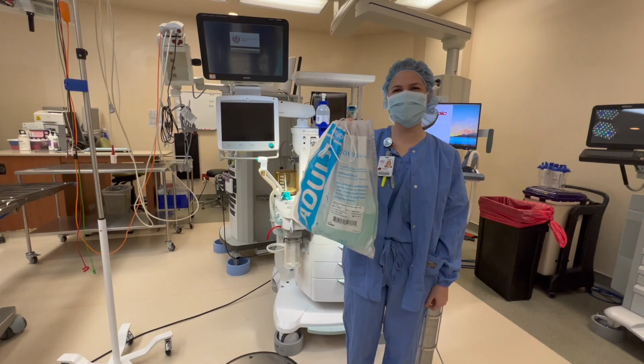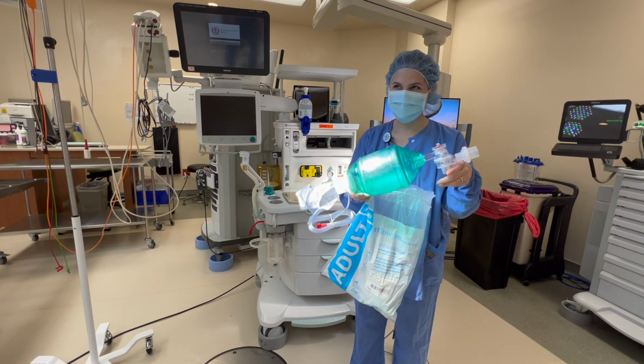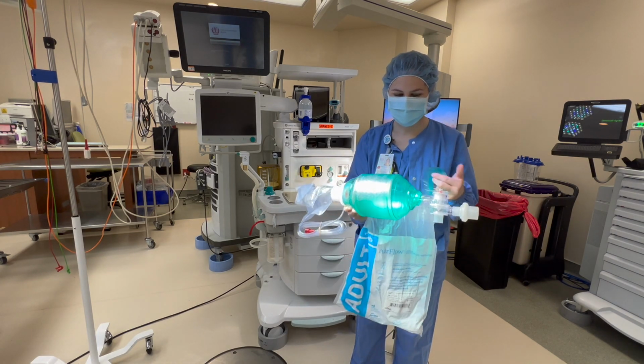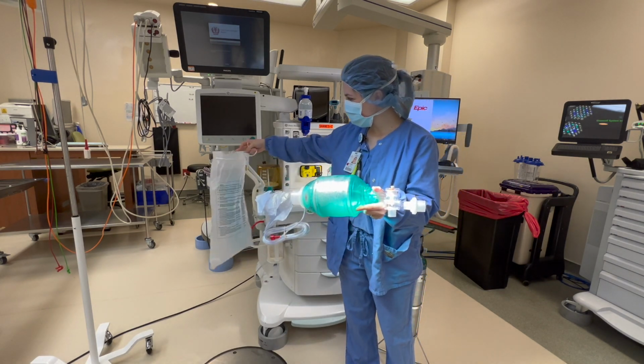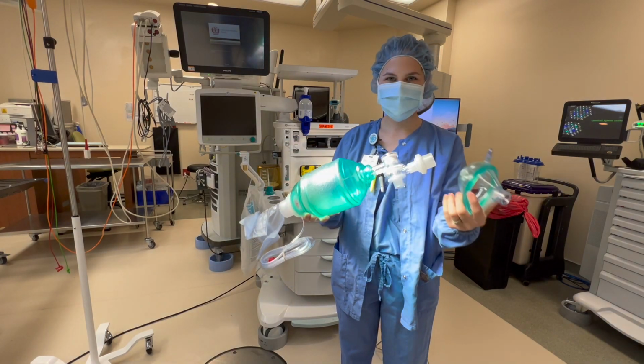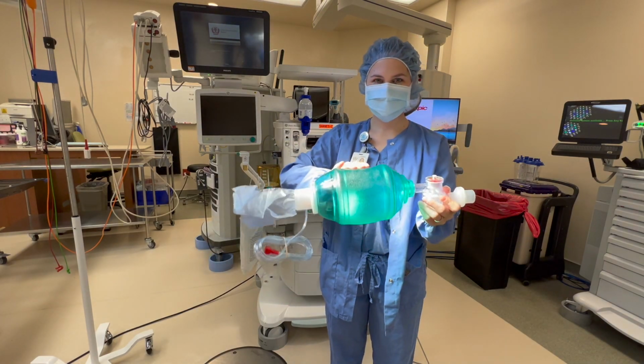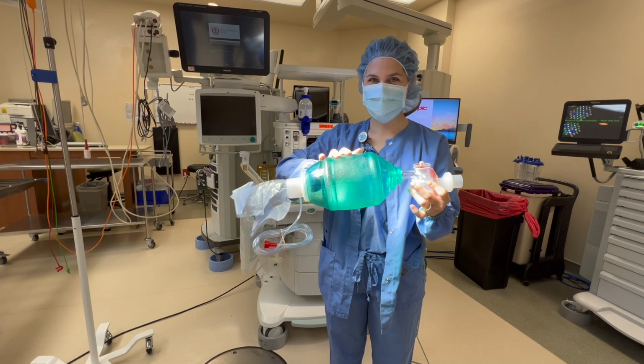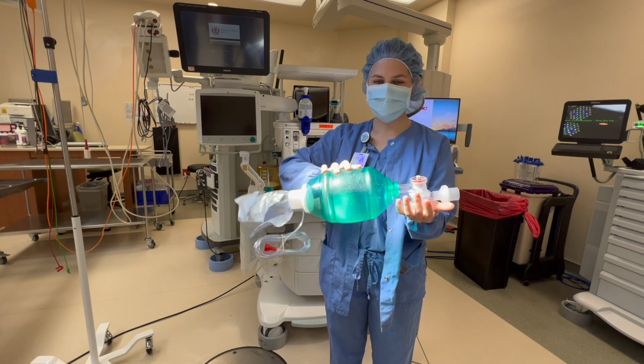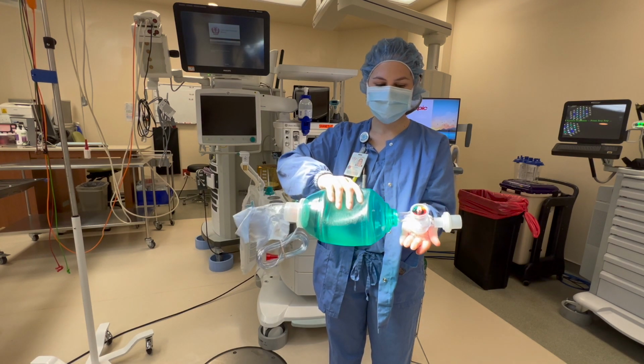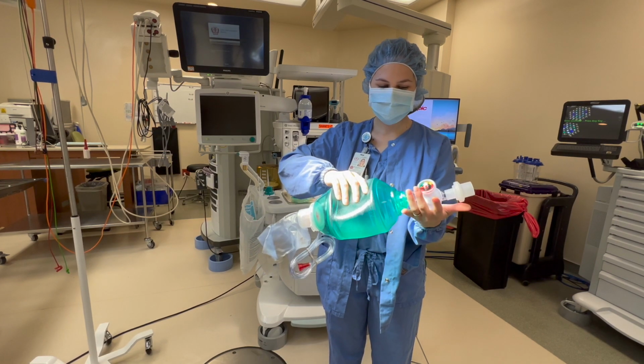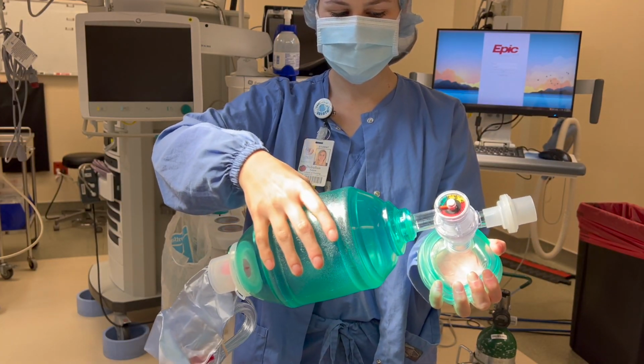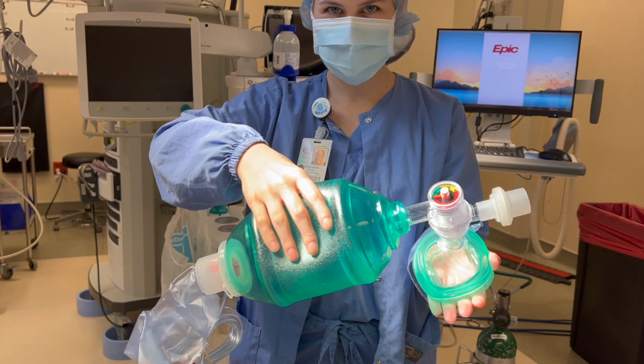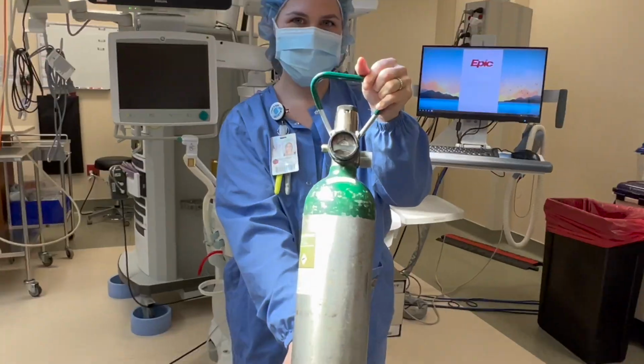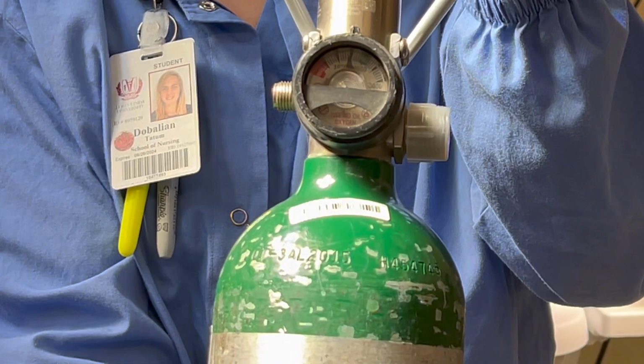Ensure you have an alternative source of ventilation by keeping a bag valve mask in the room. Make sure it's fully functioning and can self-inflate and maintain a seal for ventilation. Notice how the bag valve mask returns to its normal shape and how it maintains pressure on the attached pressure gauge. You can either do this with your hand or with the mask. Keep in mind that some sites may not want you to open and touch equipment like this, so just double check.